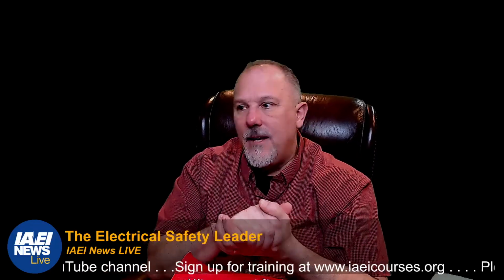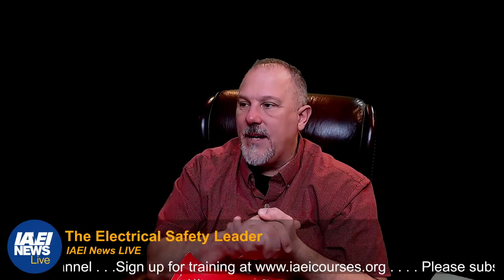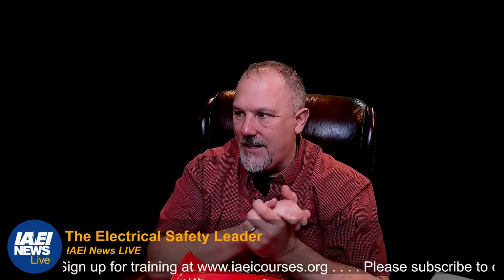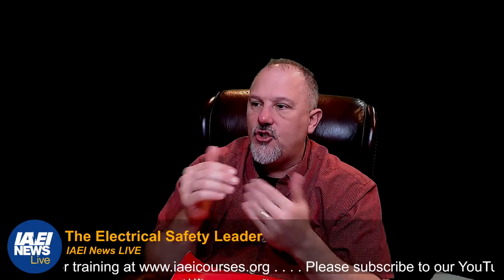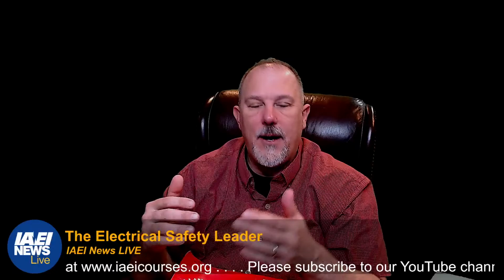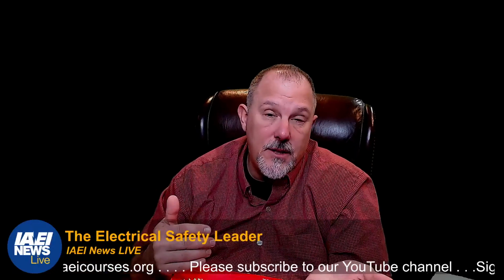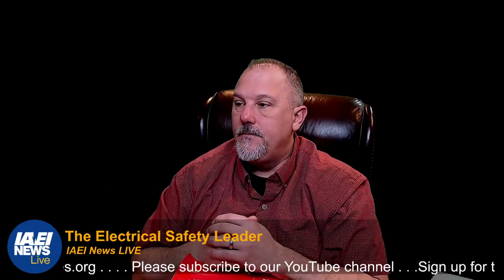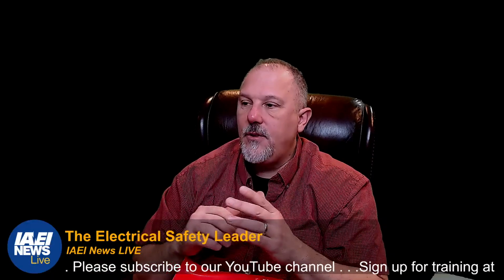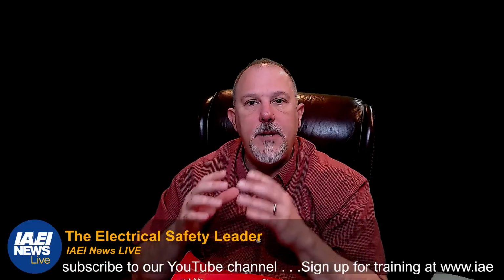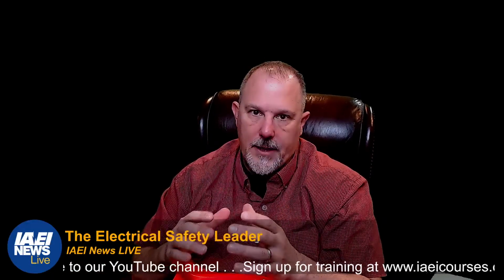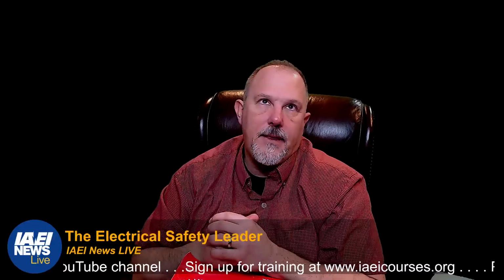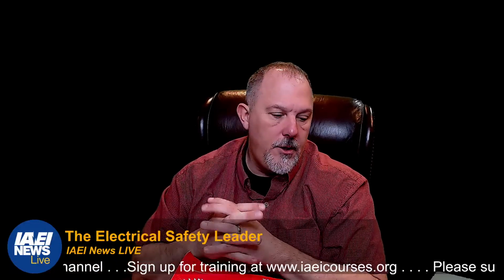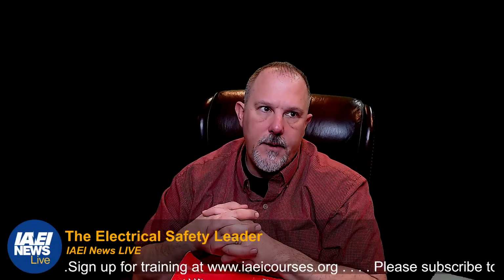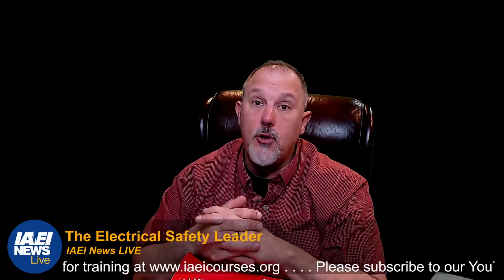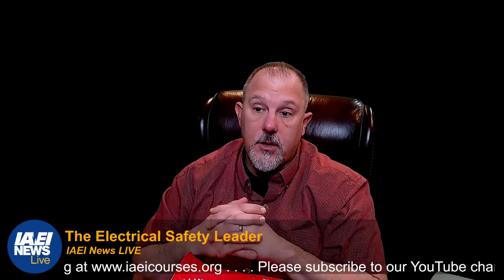Lubricate. Terminating devices, mechanical parts, and operating parts that exist to open, close, insert, and trip a circuit breaker. So now a panel board, you might have switches in there. I don't know. They're telling you that if there are any moving parts that need to be lubricated, then you need to lubricate them. I think in an enclosed panel board, you're probably limited in the amount of equipment that would need to be lubricated. I'm just going out on a limb there.